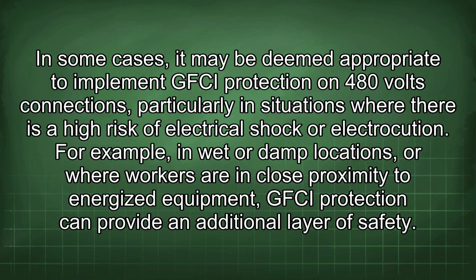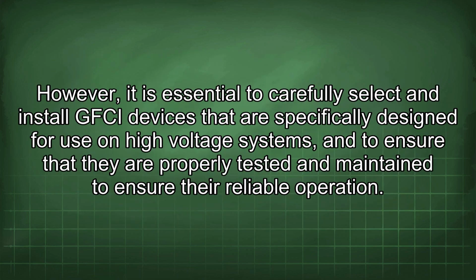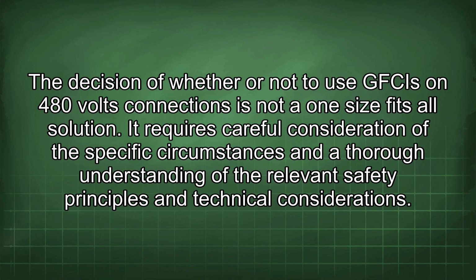For example, in wet or damp locations, or where workers are in close proximity to energized equipment, GFCI protection can provide an additional layer of safety. However, it is essential to carefully select and install GFCI devices that are specifically designed for use on high-voltage systems, and to ensure that they are properly tested and maintained to ensure their reliable operation. The decision of whether or not to use GFCIs on 480 volts connections is not a one-size-fits-all solution. It requires careful consideration of the specific circumstances and a thorough understanding of the relevant safety principles and technical considerations.